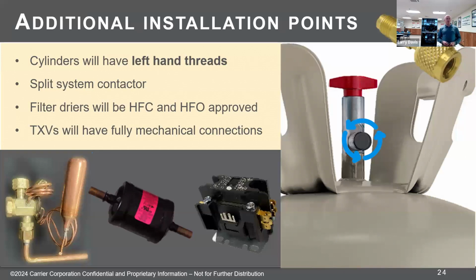If they're mechanical gauges, they're suitable for use with the 454B. I'd encourage you to have a separate set of gauges just for 454B refrigerant, so you're not cross-contaminating systems. Your digital gauges, if they can be programmed or if they have the 454B scale programmed in them, then they should be suitable for use with the 454B refrigerant. If they don't, or there's not a way that they can upload that, then they're not suitable, and you'll need to get a second set of gauges for the new refrigerant.